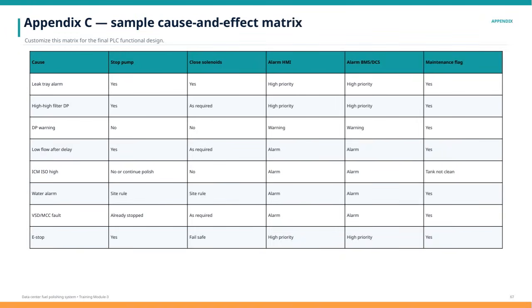Here we have a sample cause and effect matrix presented in Appendix C, designed specifically for the data center fuel polishing system. This matrix is a useful tool that you can customize to fit the final functional design of the PLC. The matrix clearly maps various causes, such as alarms or faults, to the corresponding actions that need to be taken, including stopping pumps, closing solenoids, triggering alarms on the HMI and BMS/DCS, and setting maintenance flags. For example, if a leak tray alarm occurs, the system will stop the pump, close solenoids, set high-priority alarms on both the HMI and BMS/DCS, and activate the maintenance flag.